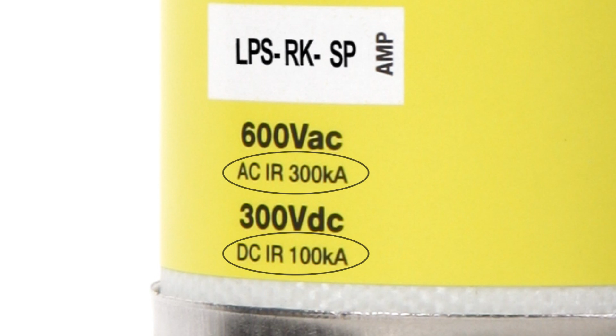Overcurrent protective devices must be able to safely interrupt destructive fault current energy. If a fault current exceeds a level beyond the device's capability, it may rupture, causing damage and posing a serious safety hazard. The rating that defines the overcurrent protective device's ability to maintain its integrity is called its interrupting rating. It's important when applying a fuse or circuit breaker to use one that can safely interrupt the largest potential fault currents. Most modern current limiting fuses have a 200 kA or 300 kA interrupting rating and can be used in just about any system without fear of misapplication.